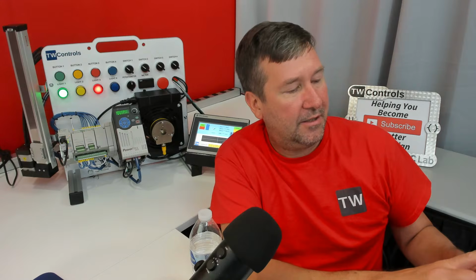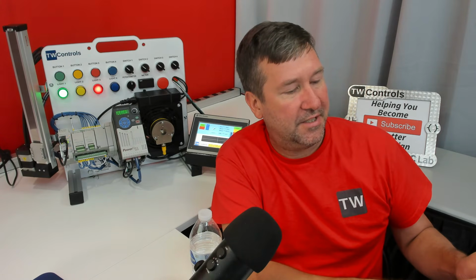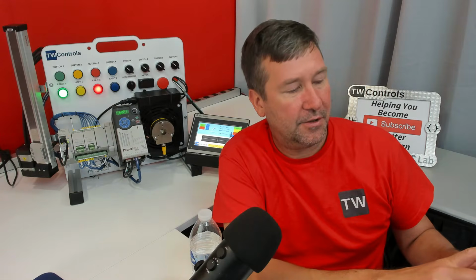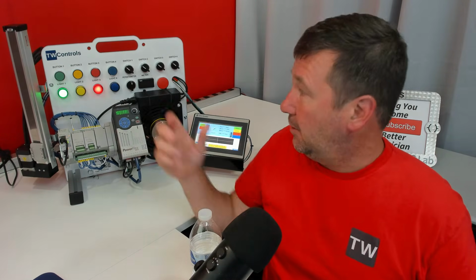Where is it exactly? Because I know he says it. I should have highlighted this. See, there's only one counter type when you execute the instructions, not an up, not a down. The false to true transition of the CTU increments the accumulated value after it equals the preset. It doesn't work that way in Connected Components.